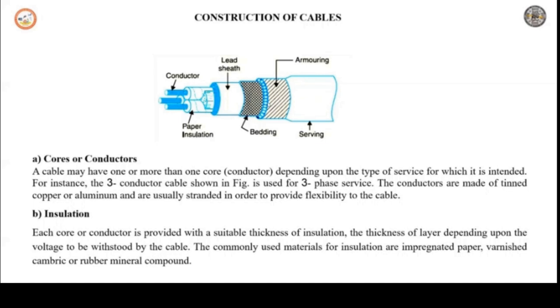Next is armoring. This layer consists of layers of galvanized steel wires which provide protection to the cable from mechanical injury. Next is serving — the last layer above the armoring. It is a layer of fibrous material like jute cloth which protects the armoring from atmospheric conditions.